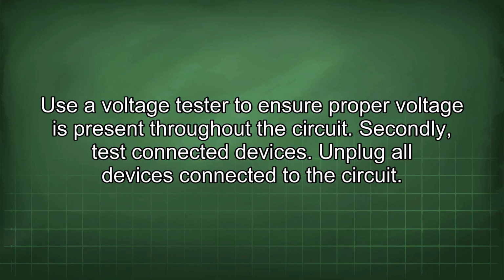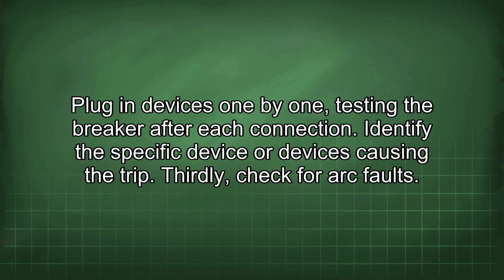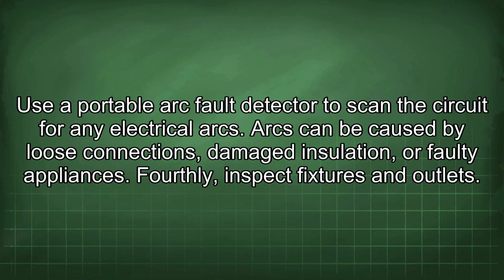Secondly, test connected devices. Unplug all devices connected to the circuit. Plug in devices one by one, testing the breaker after each connection. Identify the specific device or devices causing the trip. Thirdly, check for arc faults. Use a portable arc fault detector to scan the circuit for any electrical arcs. Arcs can be caused by loose connections, damaged insulation, or faulty appliances.